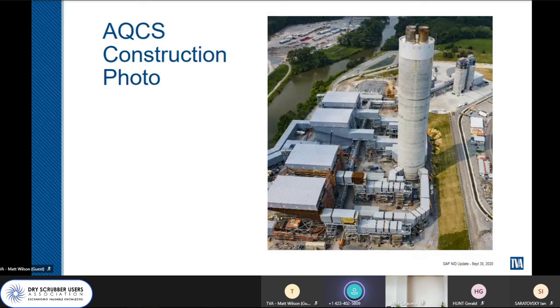That means we've got 2 ID fans pulling, balancing the draft on these balanced draft boilers all the way through this entire system. We do not utilize booster fans. So that means that we had a high suction to really design these bag houses to, which was done successfully without any issues. In the background, again, you see progress had been made on the concrete byproduct storage silos, which are shown to the right of the stack, and the pebble lime silos were built, but they are hidden by the stack itself.